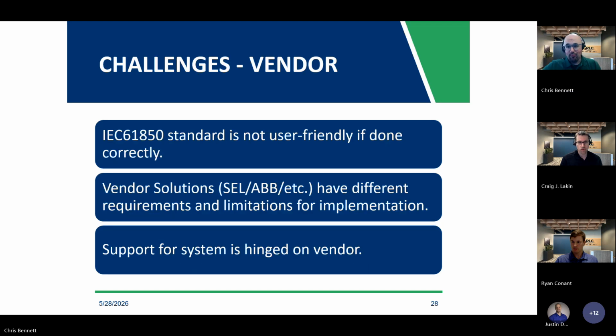A little bit on the challenges side now. These are the things that are major drawbacks. IEC 61850 is typically not new user friendly. If done correctly, there are ways to cheat the system a little bit, but your tags and your data streams can be very messy and create hazards for folks in the future if you're not careful from the get-go. So there's typically a barrier to entry there.